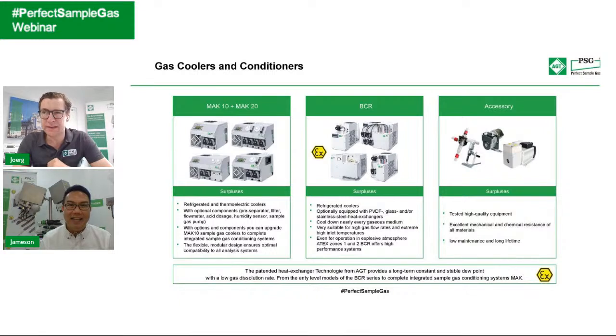Let's pretend you choose, let's say, a Peltier cooler, and the ambient temperature is too high. In these types of cases, what can you do? You can try to use an air conditioner to bring down the temperature in the room itself. But also, if there is too much water in the probe, you can think about a pre-separator, for example. Precisely, yeah. A pre-separator would be something we can recommend, and you could even install it at a later stage. We also offer the option to integrate the pre-separator inside the gas cooler.